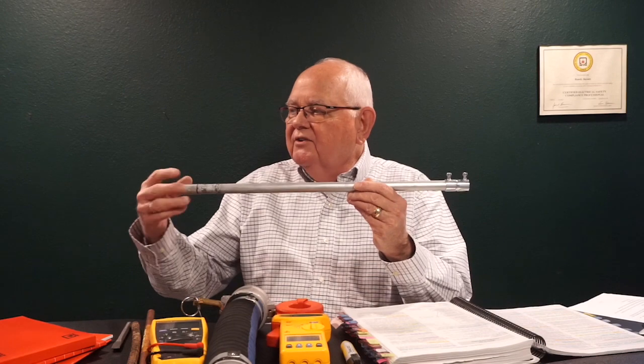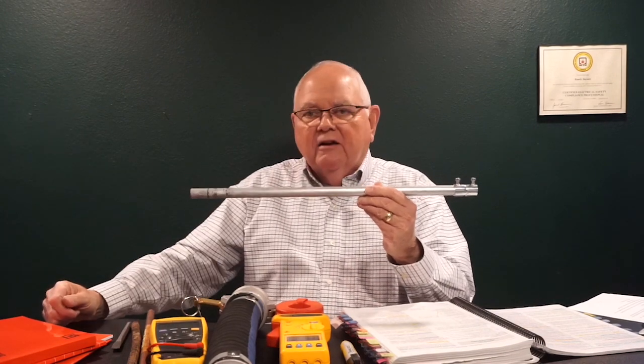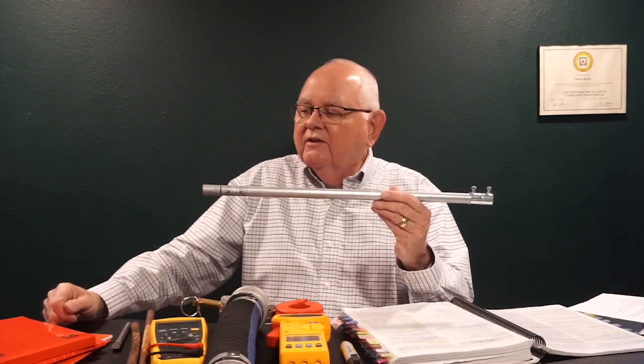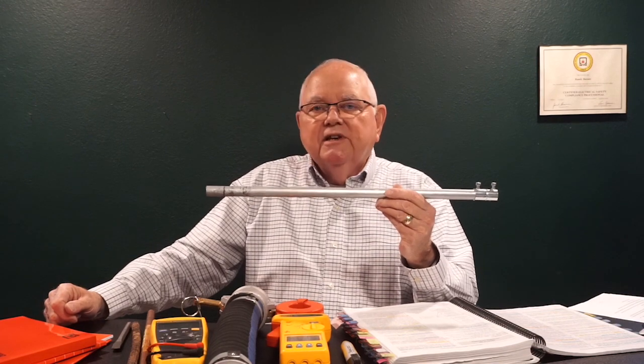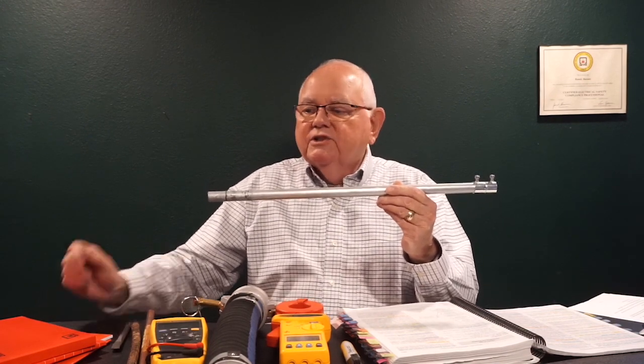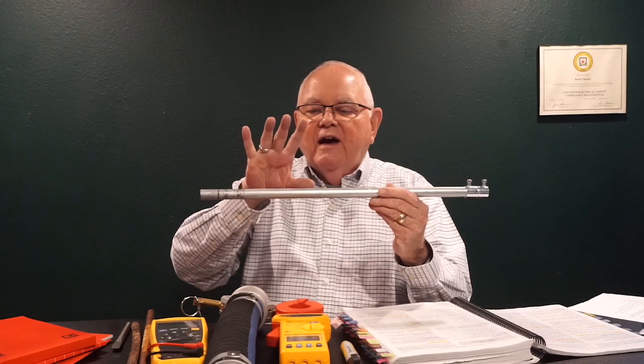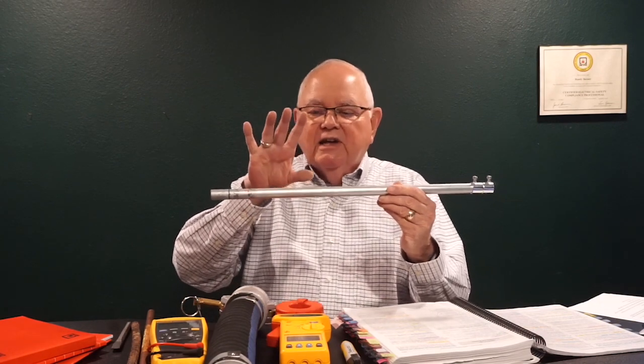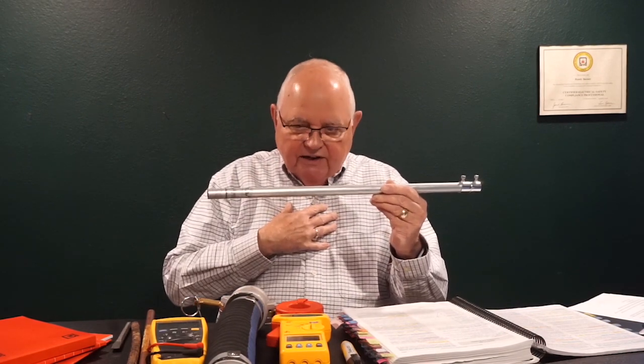This piece of conduit is connected to maybe a control panel or service panel, whatever it is over here, which is connected to the earth. And so I want to make sure if I do touch this and it's energized, I'm at the same potential. I'm standing on the earth.